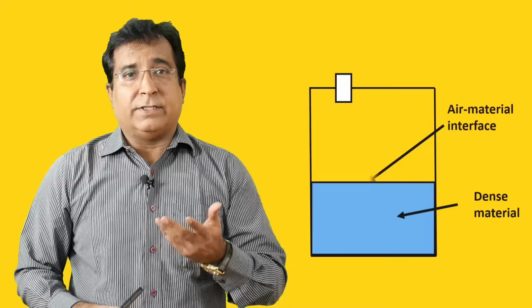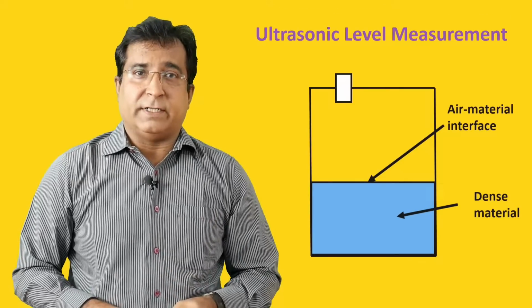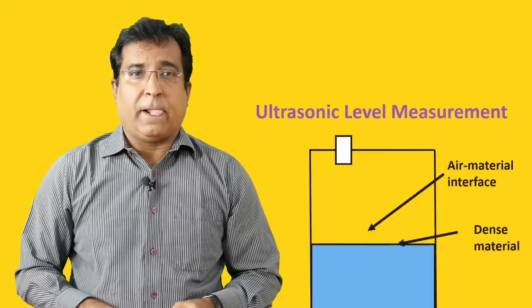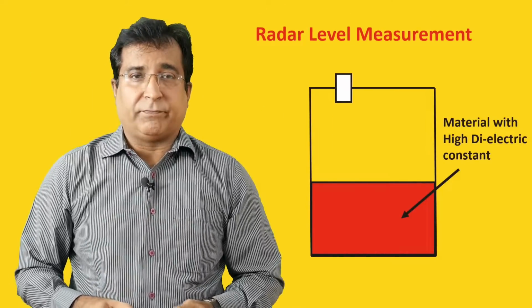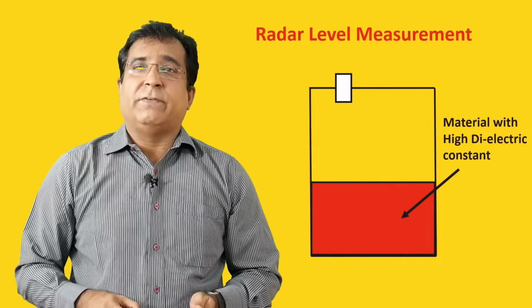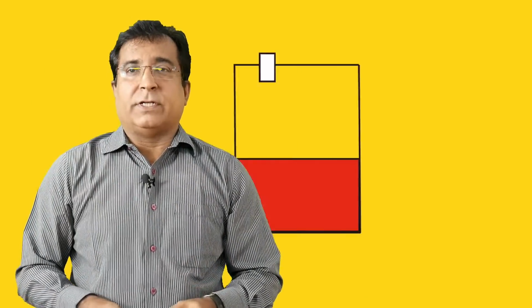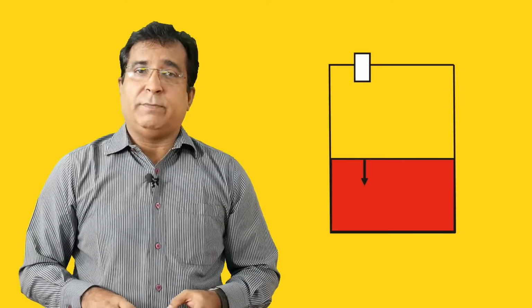Second, for an ultrasonic sensor, the condition for an echo to occur is that the sound wave must encounter a sudden change in density at the interface of air and material. So the sound wave must not be absorbed by the material, and most of it can reflect back to the sensor. While in radar level, the condition for wave reflection is a sudden change in the dielectric constant of the material. When an electromagnetic wave encounters a sudden change in dielectric constant, some of the wave's energy is reflected back to the sensor, while the balance of the energy continues to propagate into the material and hits the bottom of the tank or hopper. Again, a second reflected wave is generated that goes back to the sensor.